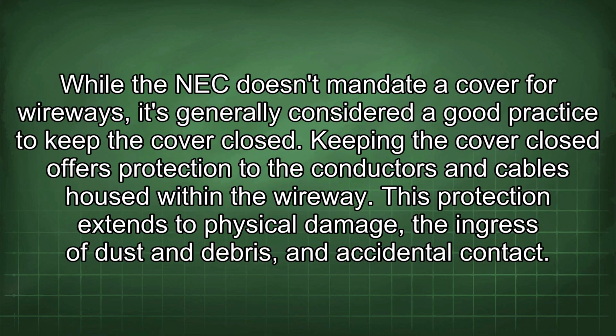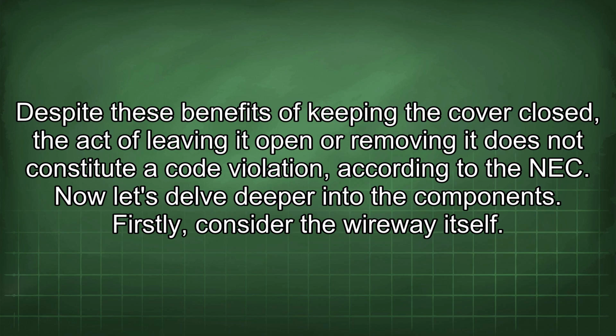While the NEC doesn't mandate a cover for wireways, it's generally considered a good practice to keep the cover closed. Keeping the cover closed offers protection to the conductors and cables housed within the wireway. This protection extends to physical damage, the ingress of dust and debris, and accidental contact. Despite these benefits, leaving the cover open or removing it does not constitute a code violation according to the NEC.